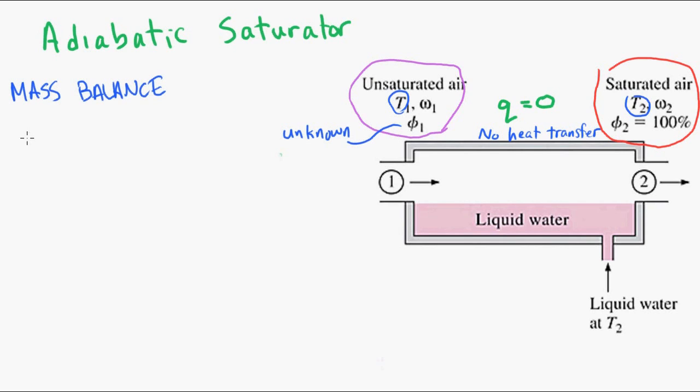So the mass going into this control volume are the mass of the air, mass of the water vapor, plus the mass of the liquid. Coming out is the mass flow of air, plus the mass flow of water vapor. So if we simplify this, the mass of the liquid is equal to the air mass flow rate, multiplied by the difference in specific humidity.